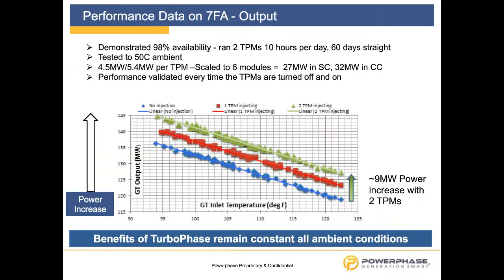From this particular project, I want to share some data with you. This is the output data. The blue lower line is the baseline of the gas turbine, which decreases over the temperature by almost 20%, to 120 megawatt. The red line is the injection of the first Turbophase module, and the green line is the injection of the second Turbophase module. In total we added 9 megawatt, and these 9 megawatt were added over the entire temperature range.